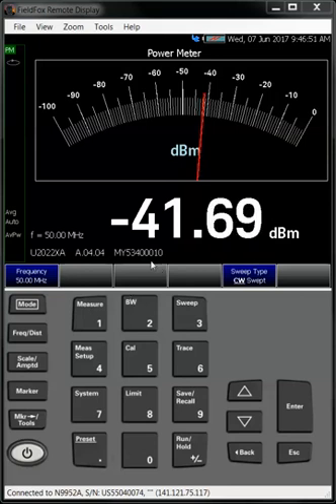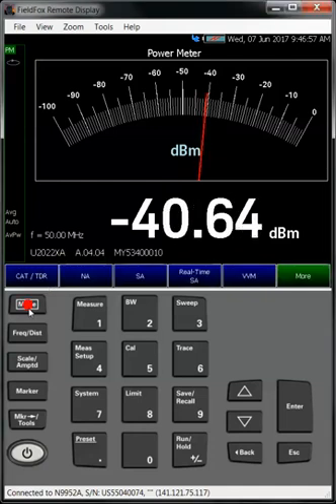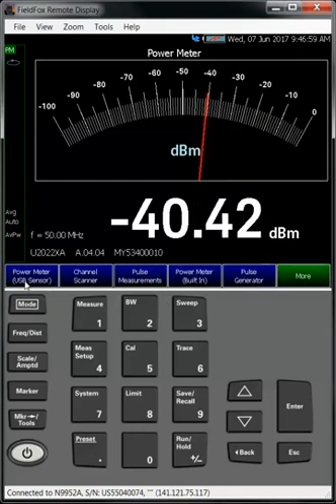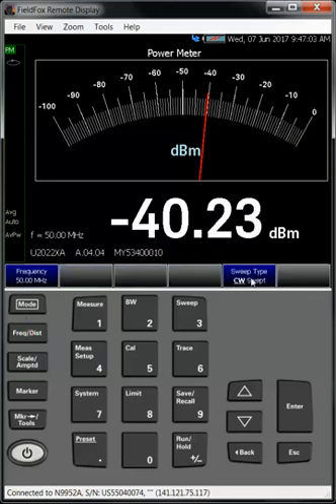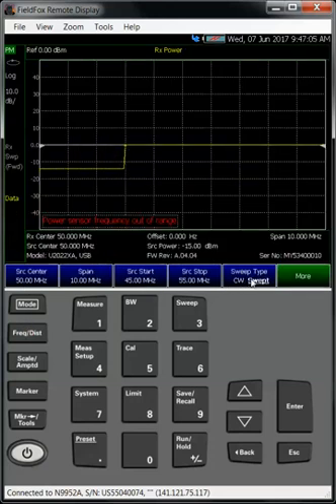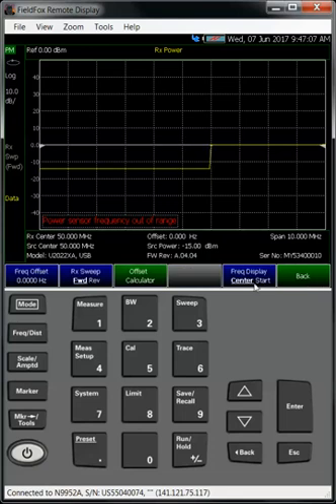So in this video, we're going to show frequency offset measurements with a power sensor. I have a U2022XA hooked up to my FieldFox, and I am in the regular power meter power sensor mode. So then I go into frequency and I switch it to swept, and then I want to enter my start-stop frequencies, so I like to see my display in start-stop.